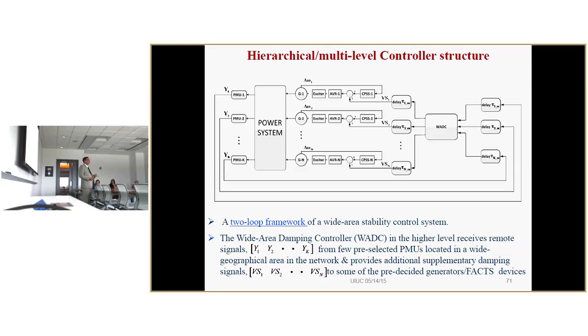One is the delay in the communication. Although they are time stamped, they are not reaching at the same time, and there will be some delay. If you use fiber optics, the delay may be about 40 milliseconds. Other technologies will have higher delays. There is a BPA report on this. So that is one problem.